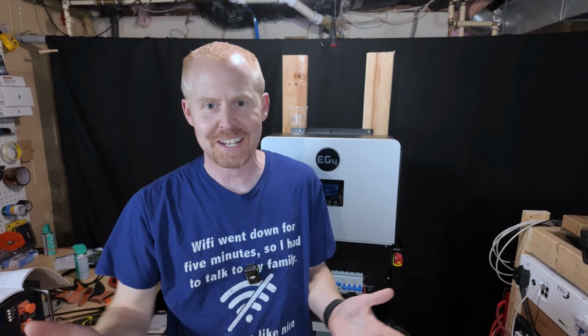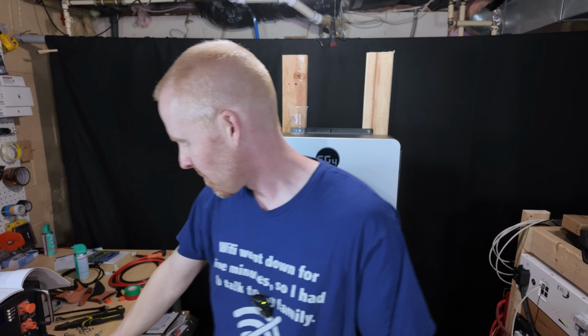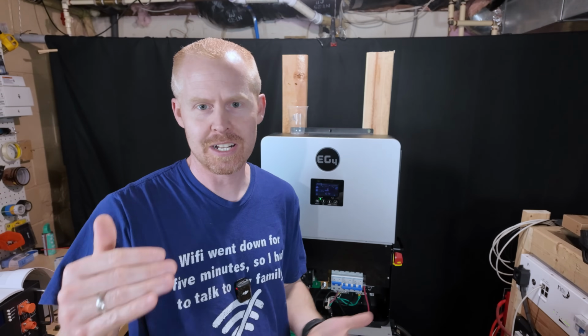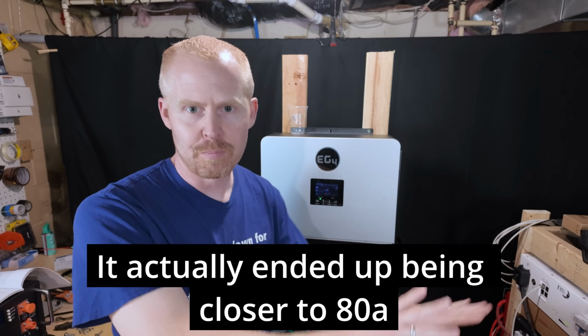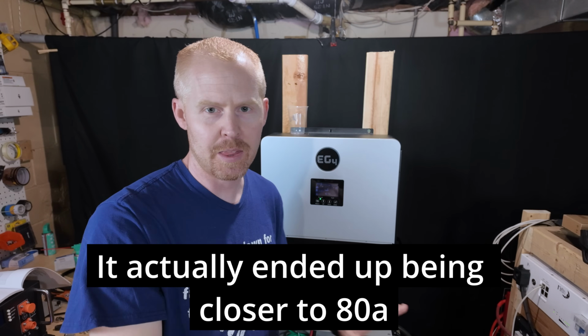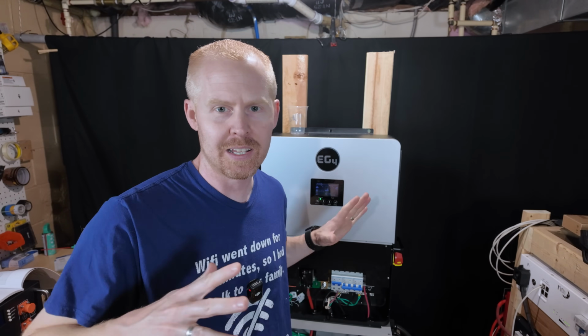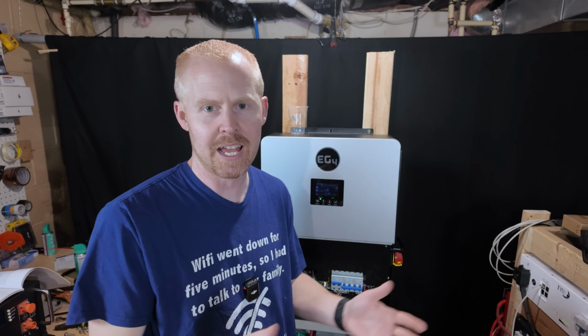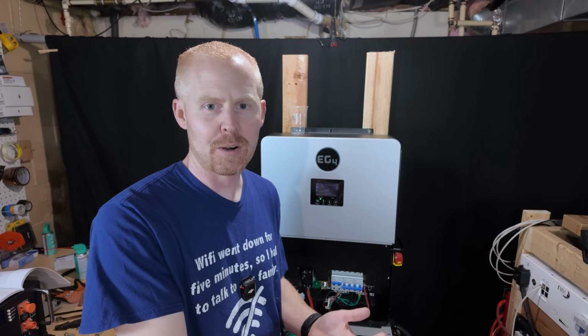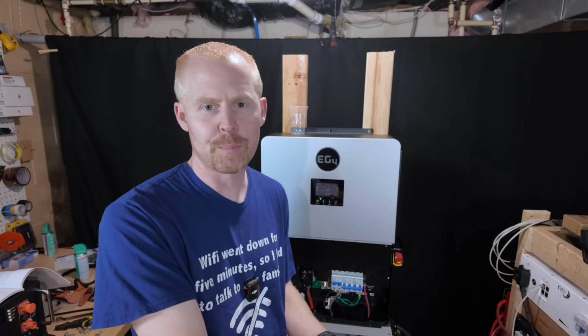So I did inadvertently test the overcurrent protection. It got over 100 amps pulling out of the battery because I punched in 100 amps on the Chargeverter, not looking at 100 amps from the battery side. So it pulled more than it was supposed to, turned off, great. So I set the Chargeverter down to 90 amps, so then it should pull close to 100 out of the battery. We'll keep an eye on that, but I want to let that run for a full hour and make sure that it actually runs properly and runs at its full output for 100% of the time.